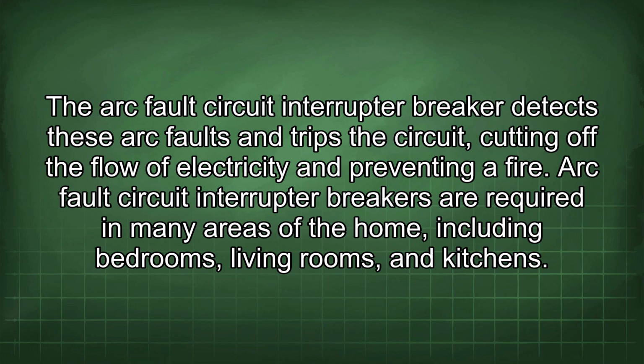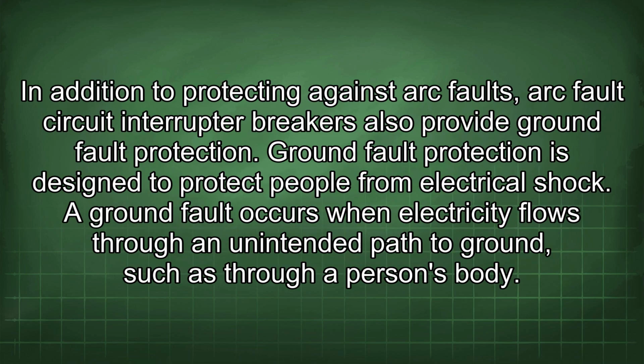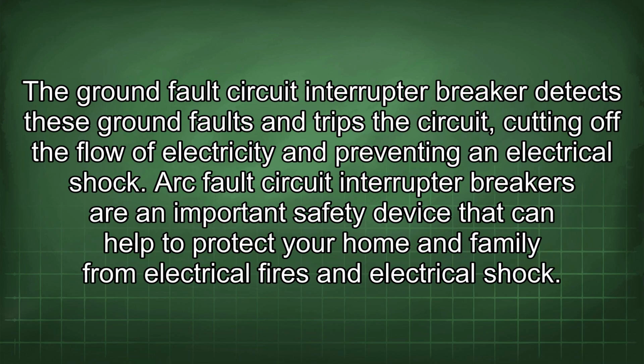and preventing a fire. Arc fault circuit interrupter breakers are required in many areas of the home, including bedrooms, living rooms, and kitchens. In addition to protecting against arc faults, arc fault circuit interrupter breakers also provide ground fault protection. Ground fault protection is designed to protect people from electrical shock. A ground fault occurs when electricity flows through an unintended path to ground, such as through a person's body. The ground fault circuit interrupter breaker detects these ground faults and trips the circuit, cutting off the flow of electricity and preventing an electrical shock. Arc fault circuit interrupter breakers are an important safety device that can help to protect your home and family from electrical fires and electrical shock.